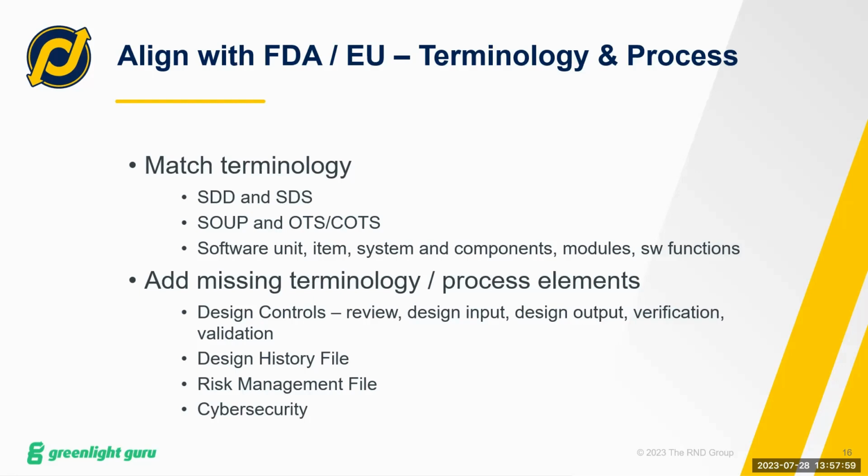The FDA, in their submission documentation, wants a software design specification. Those two are very similar documents. They could even be one for one. In our case, they are a match. And so we make sure we call out that this SDD is equivalent to an SDS. You can do that in your text, but oftentimes it'll be in your glossary or terminology sections of your process, just like I said, to connect those dots.